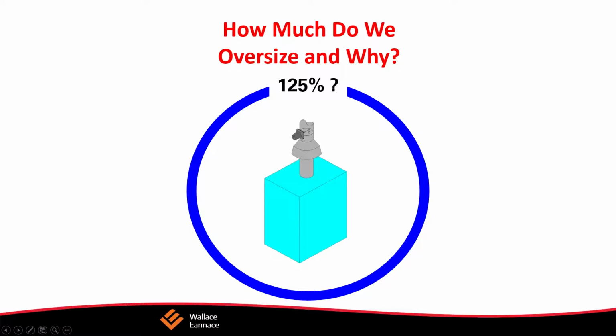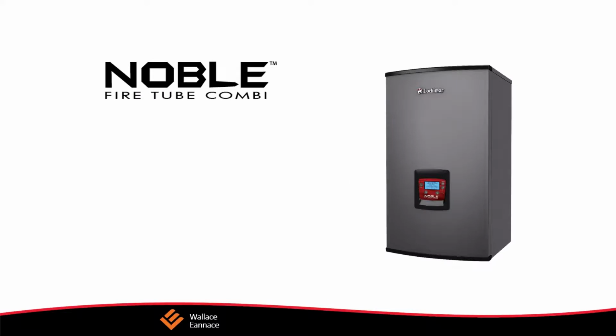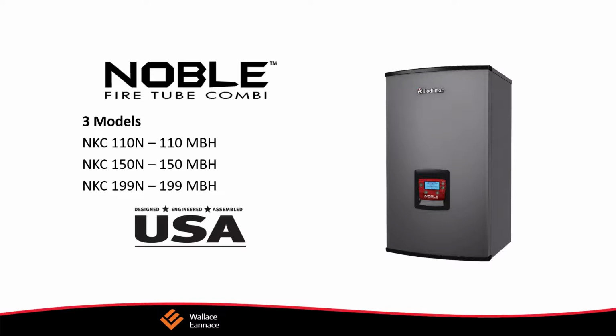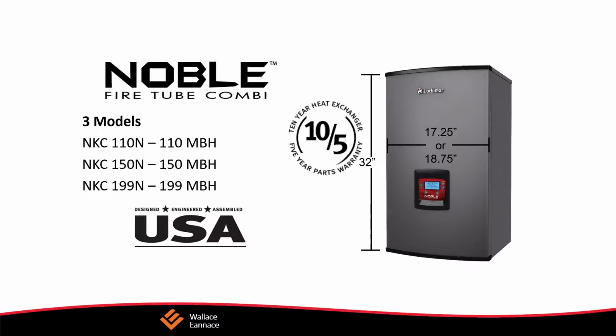Now, also one of the things you have to consider when you're selecting a boiler is, do you oversize it, and why? Some of the big concerns, for example, in a simple house: a building will typically have 35 BTUs per square foot. So if I have just a simple 1,000 square foot house, it'll only have a 35,000 BTU load. Yet if I have a single shower in that house, a typical shower uses about 2.5 gallons per minute. Each gallon per minute will use about 40,000 BTUs.